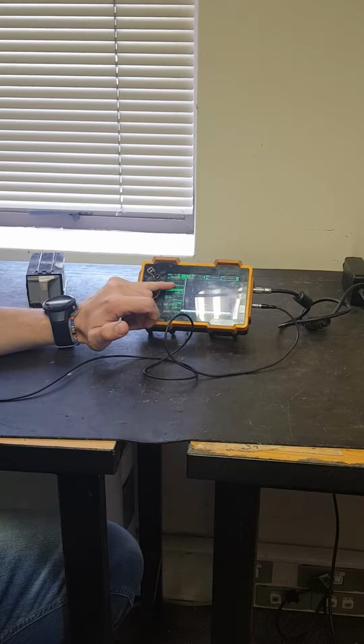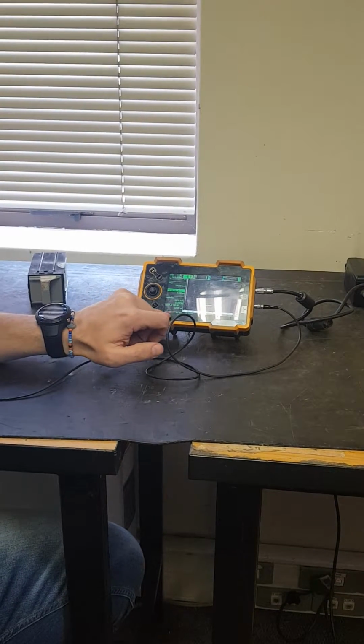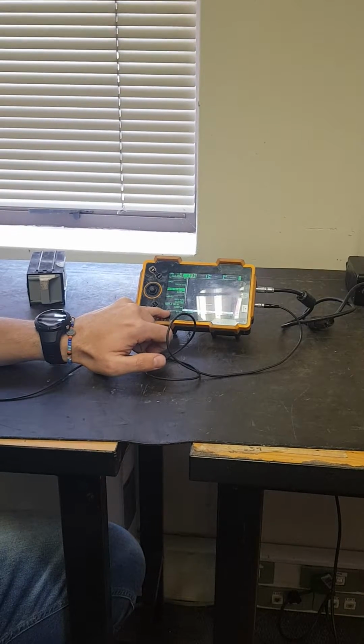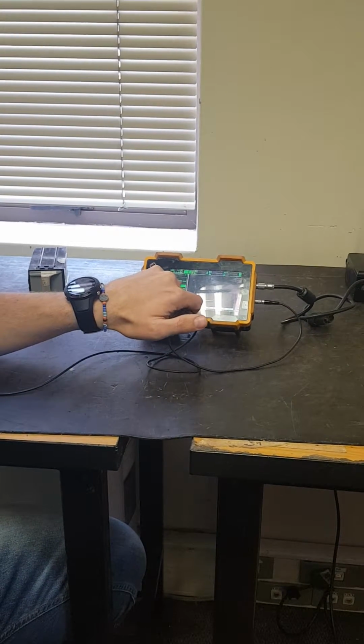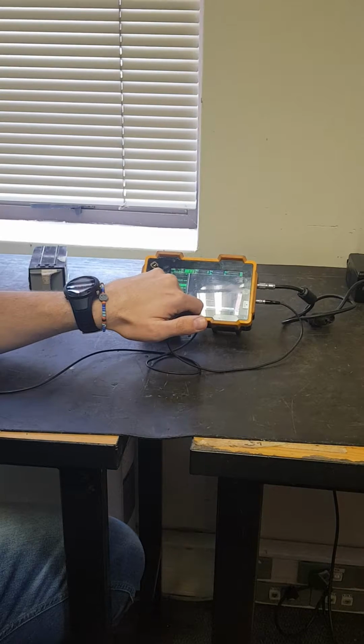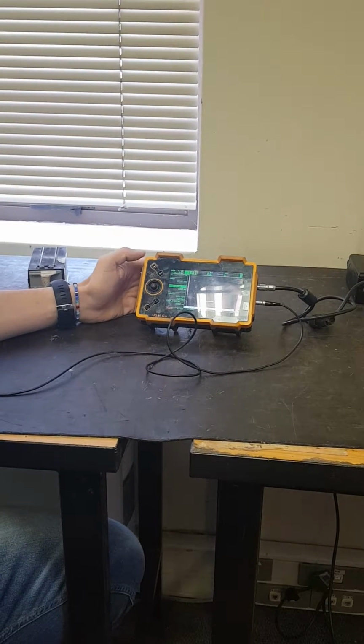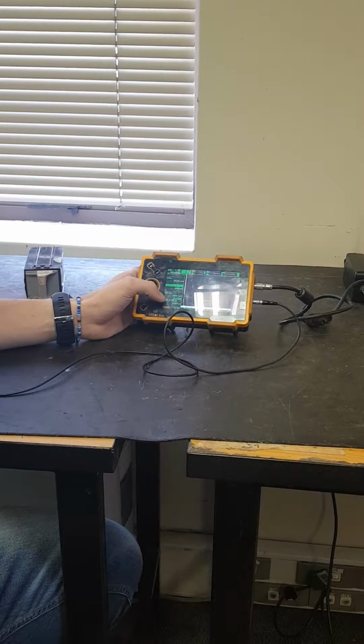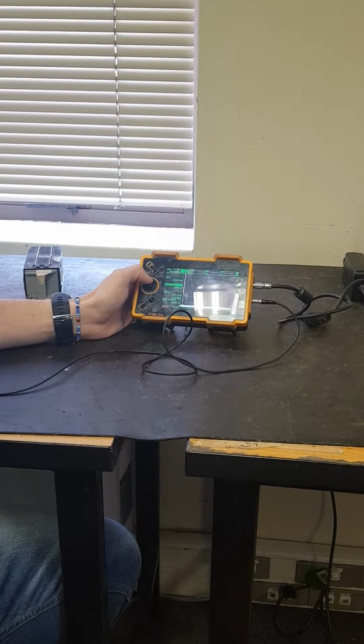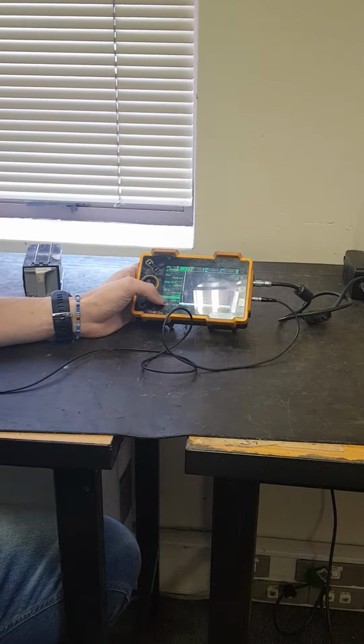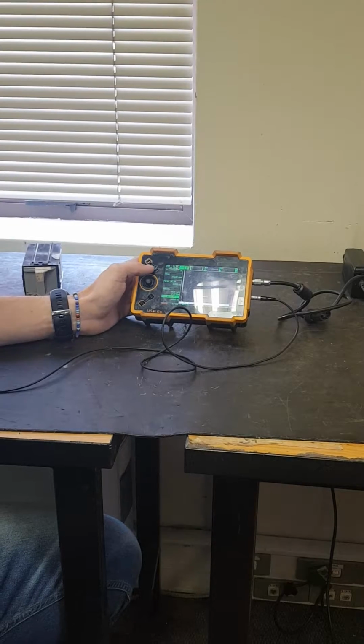So I want you guys to go to range. You go to your range menu, and you'll notice that it is red. You edit your range, so it's on 100. You edit your probe delay, so it's on 0. You edit your velocity, so it's on 5920 meters per second, and your display delay, just leave that on 0.